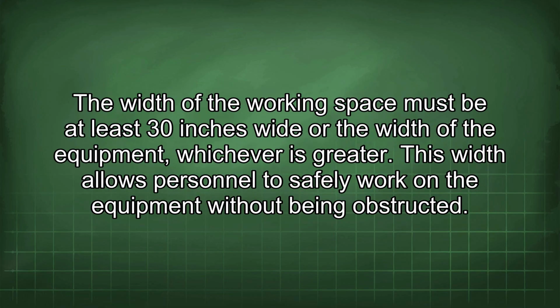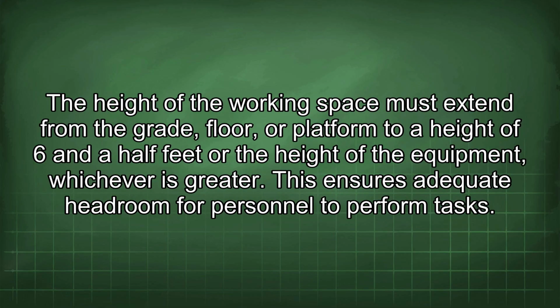The width of the working space must be at least 30 inches wide or the width of the equipment, whichever is greater. This width allows personnel to safely work on the equipment without being obstructed. The height of the working space must extend from the grade, floor, or platform to a height of 6.5 feet or the height of the equipment, whichever is greater. This ensures adequate headroom for personnel to perform tasks.